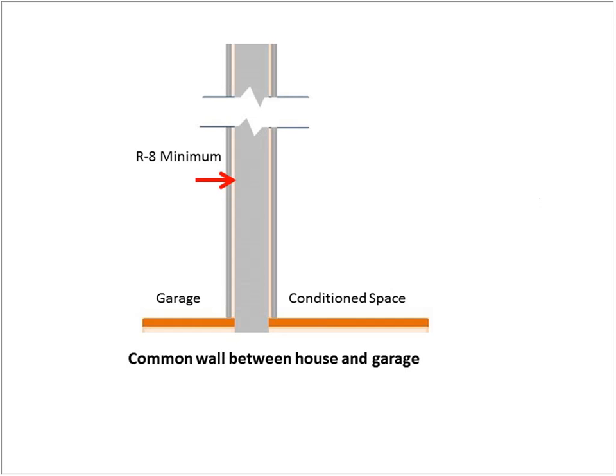Here's an example of the common wall between the house and the garage, and the garage is on the left of that cross-cut of the wall cavity, and the conditioned space is on the right. The wide gray bar going up is the ductwork, and the arrow is showing where the R8 minimum would need to be. Now, if you wanted that duct to be in the thermal envelope, then you'd have to change that R8 to an R20, which means that it might be beneficial to bulkhead that wall so that you can get a full R20 in there. Or if it's a floor cavity, then you would bulkhead it so that you could get a full R30.